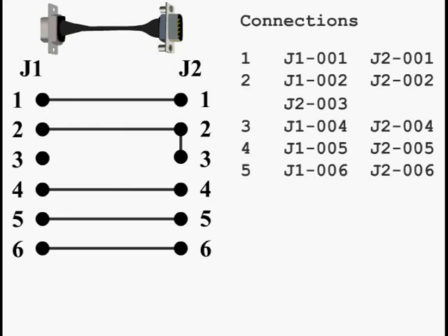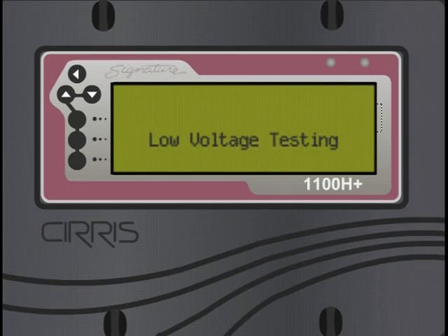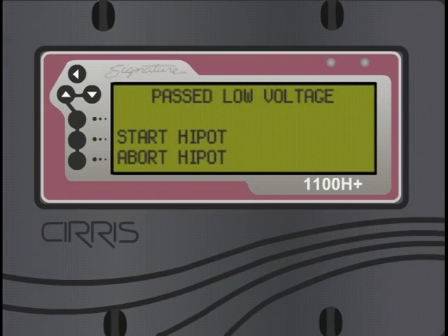Cirris hipot testers first do a low voltage scan of all points looking for opens, shorts, and miswires before doing the hipot test. If the continuity test passes, a net by net hipot test proceeds as follows.